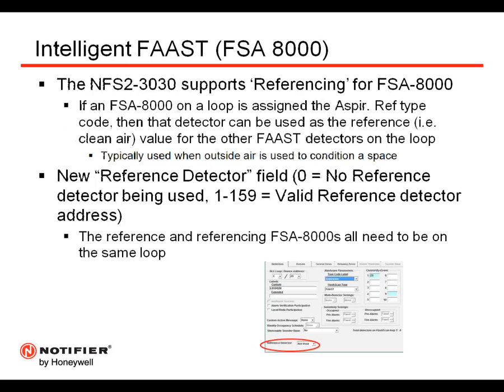And the NFS2-3030 with firmware version 20 or higher supports referencing for FSA 8000. So if an FSA 8000 on a loop is assigned as the aspiration reference type code, then that detector can be used as a reference, or therefore the clean air value, for the other FAAST detectors on the loop. Typically, someone would use a referencing detector in an application where they want to use outside air to condition the space. In today's world, a lot of people are going green and trying to save on their energy costs. So in certain applications, they prefer to use outside air to condition the space. One concern of using outside air is that if there's a contaminant coming in from the outside air into the space, the reference detector can set up what that clean air value is.